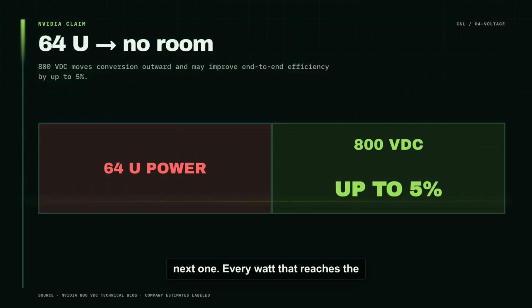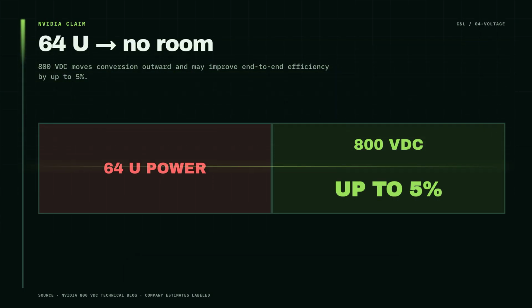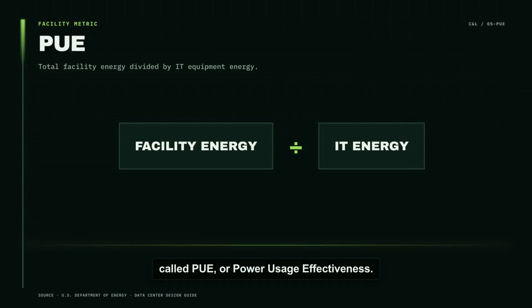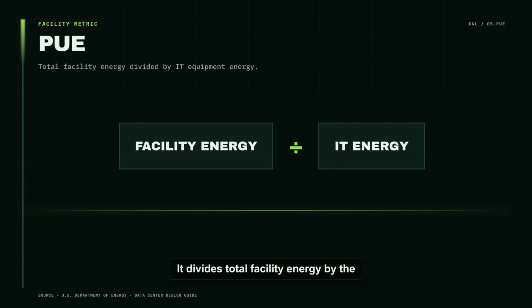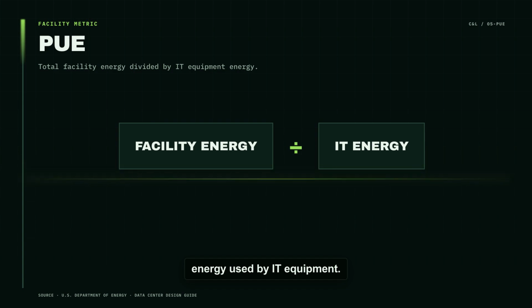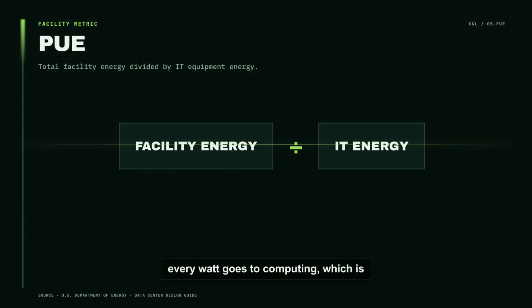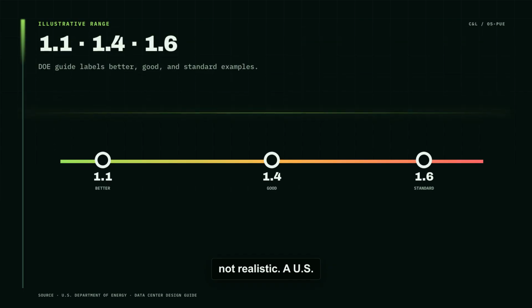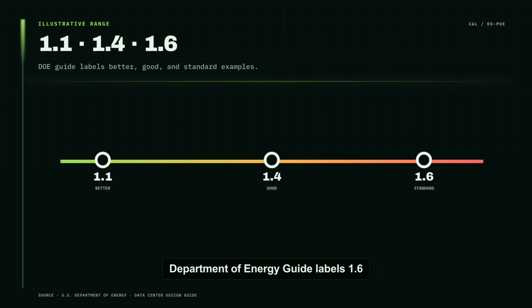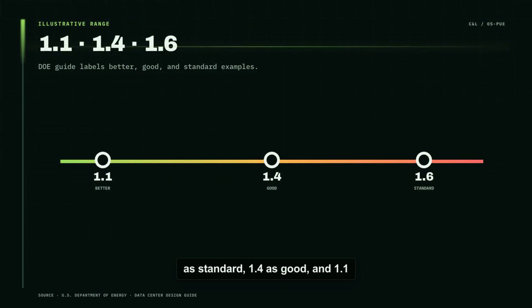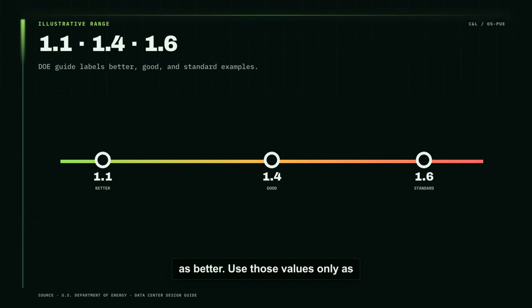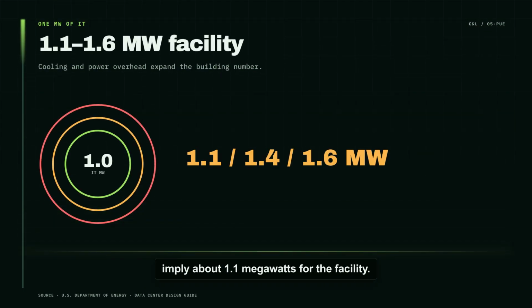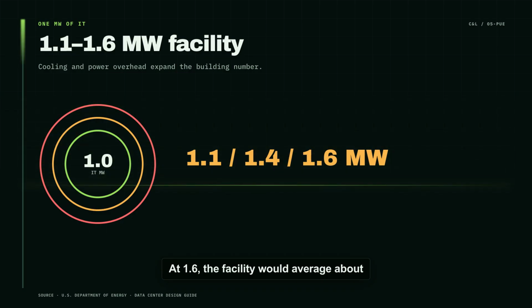Every watt that reaches the processors eventually becomes heat, and the rack's number is not the building's number. Data centers track overhead with a metric called PUE, or power usage effectiveness. It divides total facility energy by the energy used by IT equipment. A perfect score of 1 would mean every watt goes to computing, which is not realistic. A U.S. Department of Energy guide labels 1.6 as standard, 1.4 as good, and 1.1 as better. Use those values only as an illustration. If the IT equipment averaged 1 megawatt, a PUE of 1.1 would imply about 1.1 megawatts for the facility. At 1.6, the facility would average about 1.6 megawatts.